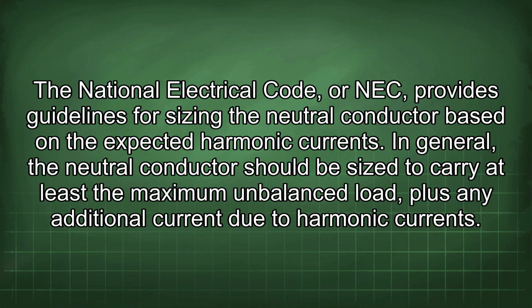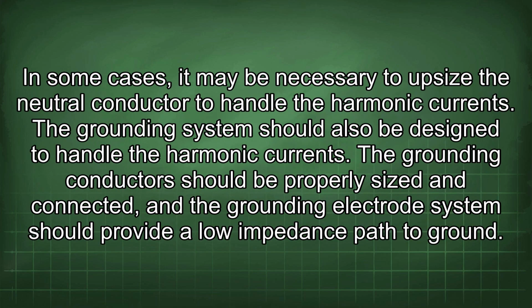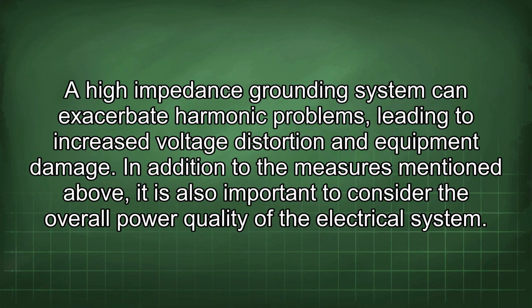The National Electrical Code, or NEC, provides guidelines for sizing the neutral conductor based on the expected harmonic currents. In general, the neutral conductor should be sized to carry at least the maximum unbalanced load, plus any additional current due to harmonic currents. In some cases, it may be necessary to upsize the neutral conductor to handle the harmonic currents. The grounding system should also be designed to handle the harmonic currents. The grounding conductors should be properly sized and connected, and the grounding electrode system should provide a low impedance path to ground. A high impedance grounding system can exacerbate harmonic problems, leading to increased voltage distortion and equipment damage.